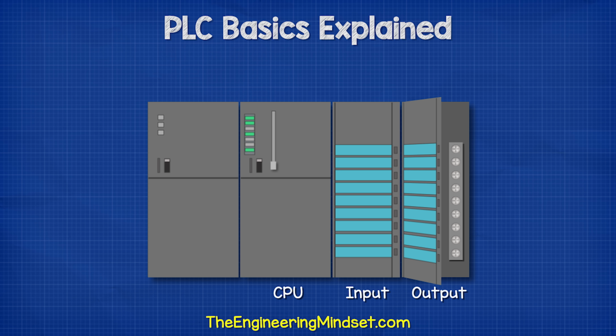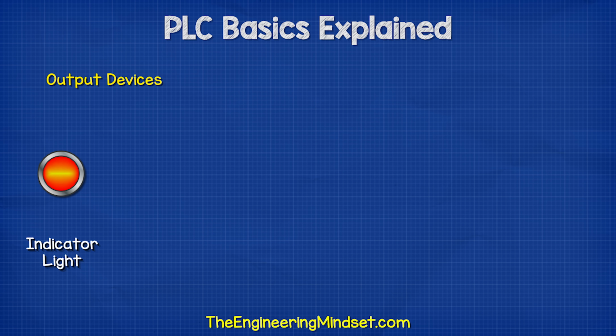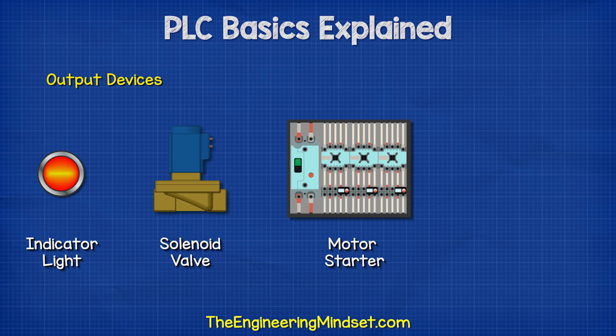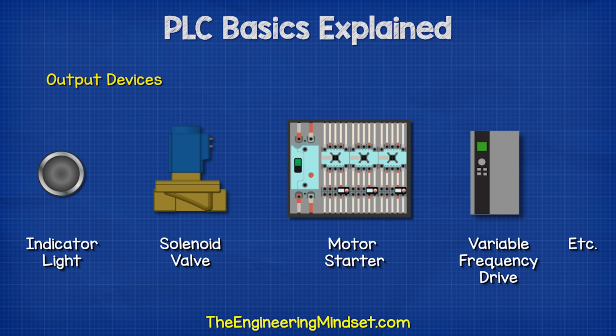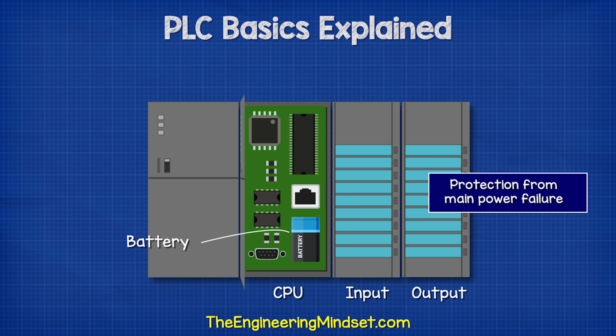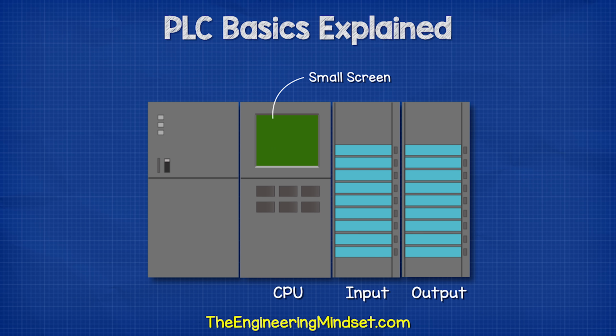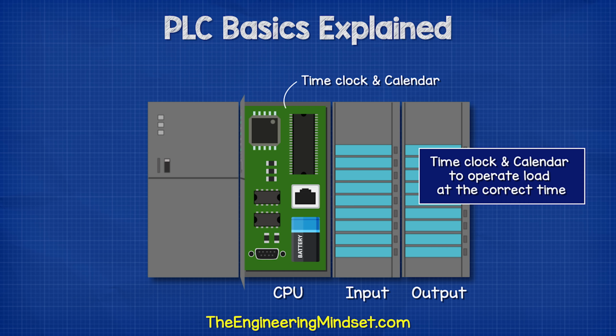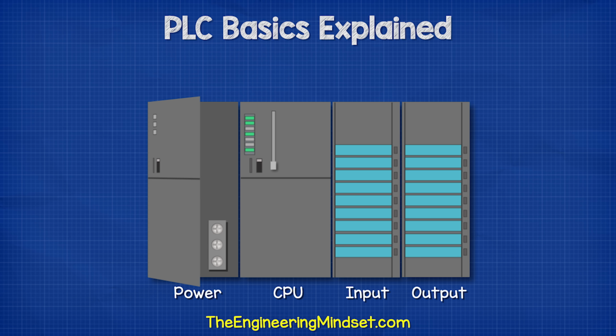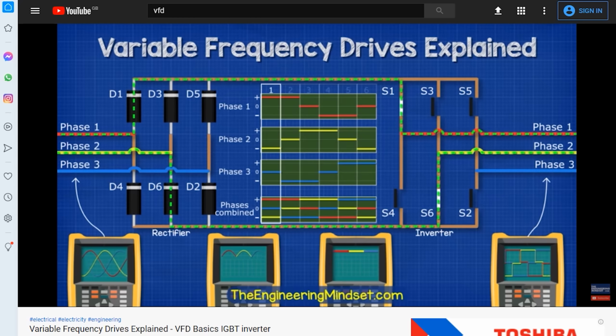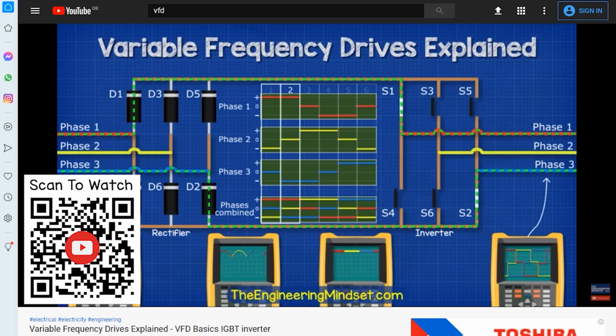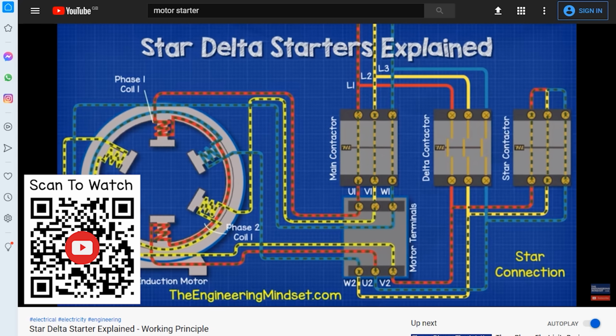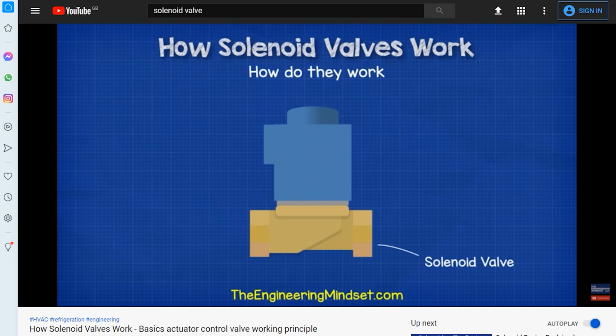Then there's the output modules, or field output devices. This is providing the signal to the device we are controlling. For example, a simple indicator light, a solenoid valve, a motor starter, a variable frequency drive, etc. There are some other parts, such as a battery to keep the PLC alive in the event of a power failure. There might be a small screen for a user interface to allow some configuration. There will need to be a time clock and calendar to operate a device at the correct time. And there will also need to be a power supply to provide the low voltage used by the CPU as well as the input and output modules. By the way, we have covered variable frequency drives, motor starters, and solenoid valves in detail in our previous videos. Do check those out, links can be found in the video description down below.